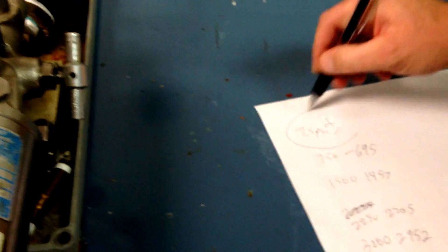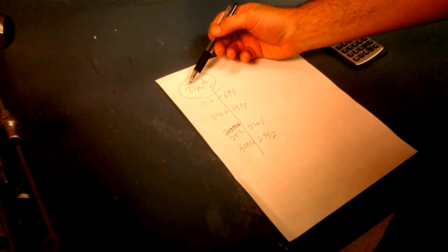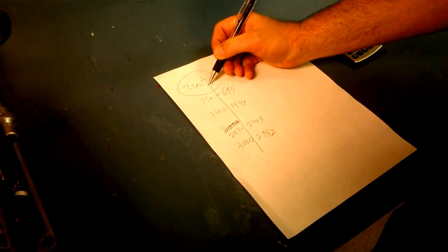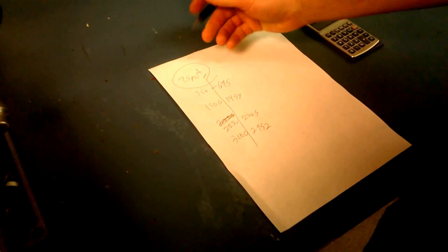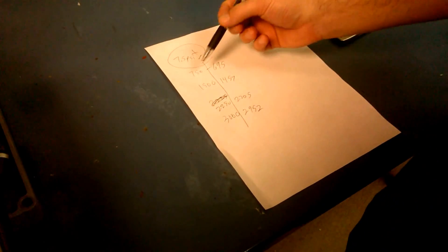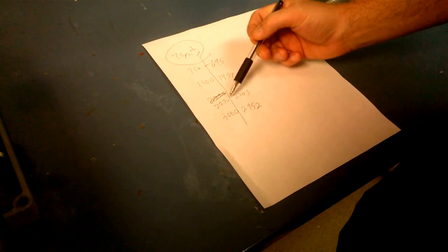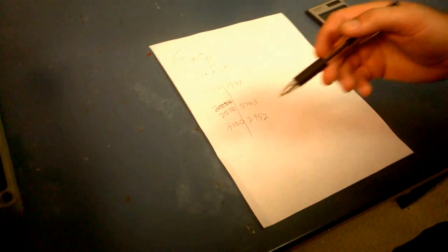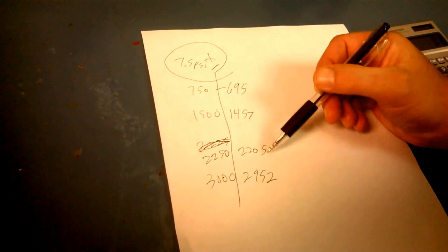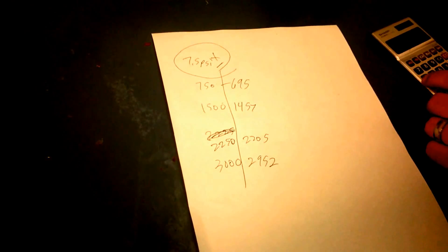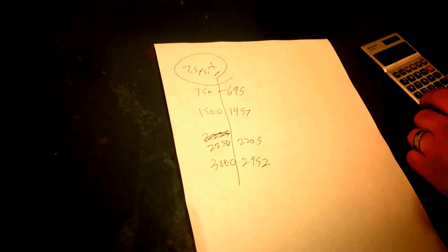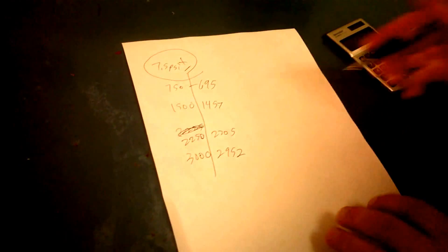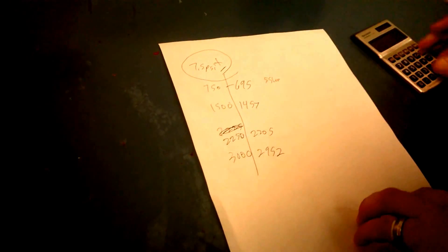So, if you look at my sheet of paper over here, here's our tolerance, plus or minus 7.5, that's our tolerance. How far off it can be at any reading. Here's the test points, 750, 1500, 2250, and 3000. Now here's what we actually got. So 695 is, that's 55 low. Way out.